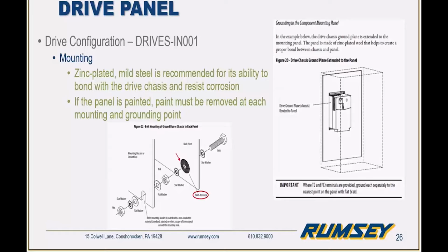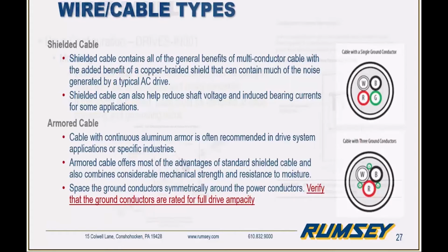Jared, if I can just jump in real quick on that one, I want to double stress the galvanized back panel use. I know sometimes we tend to get looked at a little funny because everybody likes painted panels, but high frequency noise likes surface area to be gotten rid of, as opposed to a safety ground, right? Which is a point solution. So not having all of the paint on a galvanized panel does a few things for you.